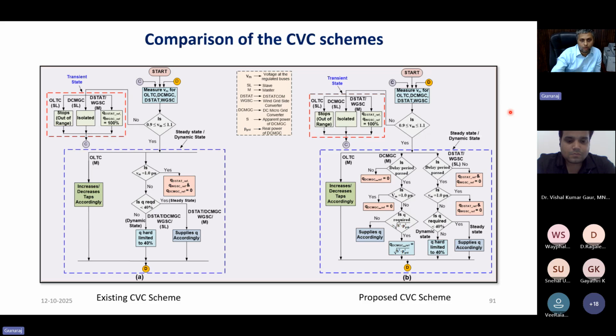As you can recall, in the earlier part of my discussion, I've already mentioned that mechanical OLTC tap changing is not recommended too frequently because it will affect the life of the OLTC tap changer. So you ensure that a significant amount of voltage change happens for a considerable amount of time, and then the OLTC tap changing may be initiated.